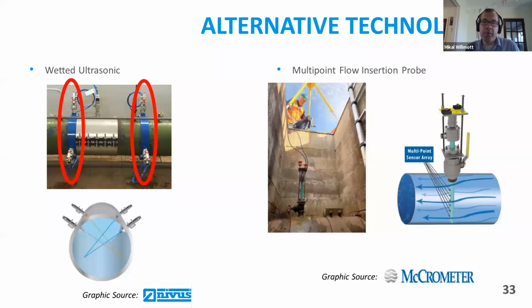Another product well worth considering, and again, we've used it in Severn Trent, and we're putting them on our transmission main, is a multi-point sensor. And this goes into the main. It has several different points, and it picks up the different velocities you've got on there. So again, it helps give you a picture of what's happening in there. Again, they're well worth looking at. Evaluation International, University of Utah have done some testing on these meters. Andy, I think it's back over to you now.